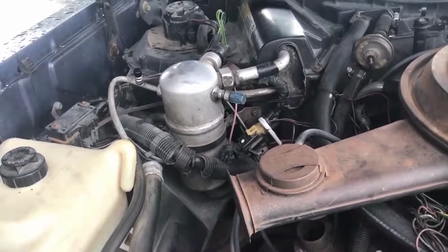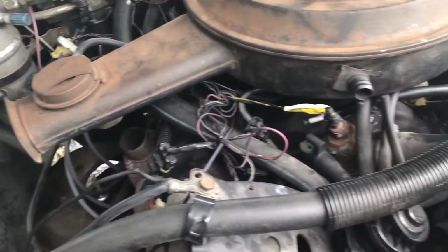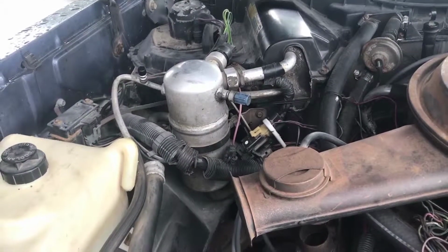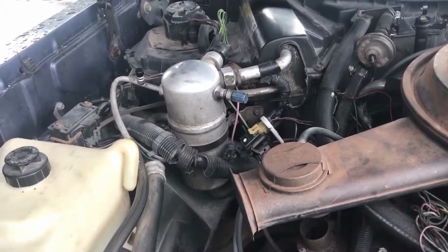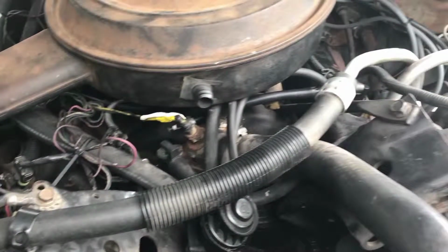The diagram I showed you doesn't have this accumulator like this system does, which is the tall silver thing there. This makes sure that if the refrigerant doesn't go into a completely vapor form, if some of it's still liquid, it catches it there in the accumulator. That way the liquid doesn't reach the compressor, and the compressor is not designed to handle that. It would eventually ruin the compressor. Actually, probably quickly.